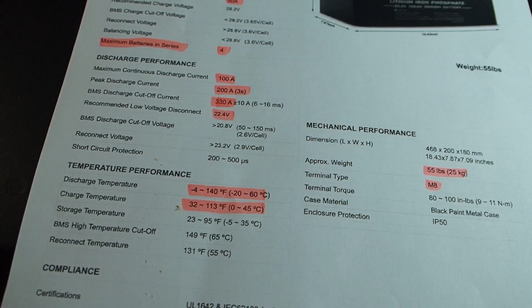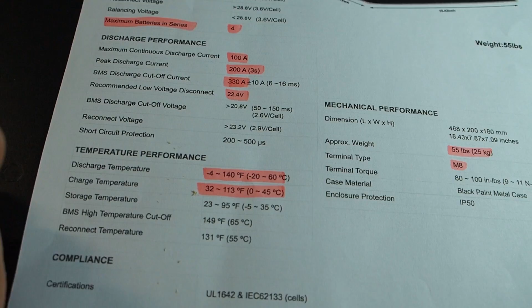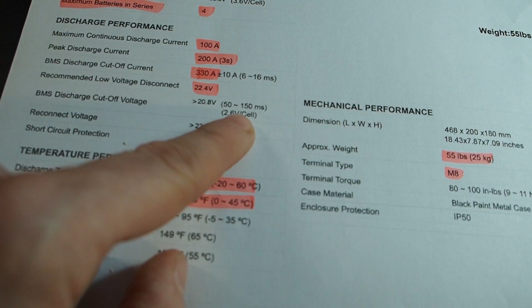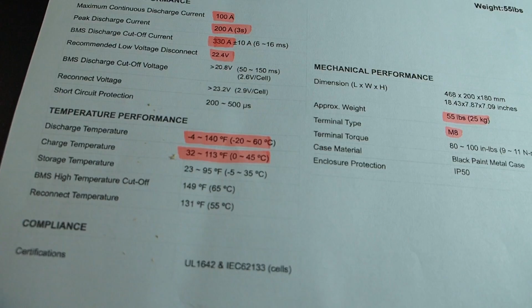Now next, you should not discharge the battery more than down to 22.4 volts. That's really important if you want to get more lifetime out of your battery. If you don't disconnect the battery when the voltage goes below that point, the BMS is going to cut off the voltage at 20.8 volts. And it's going to reconnect at 23.2 volts.